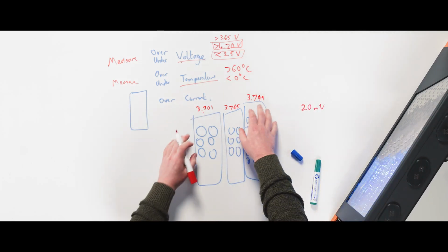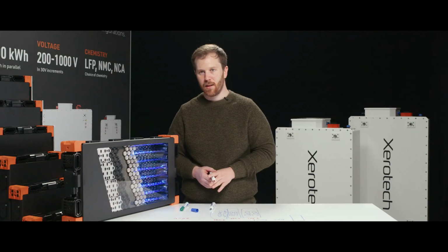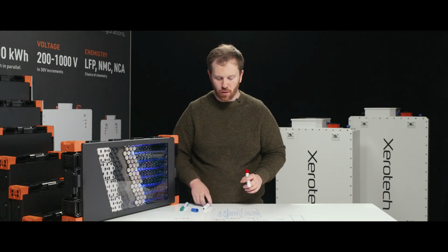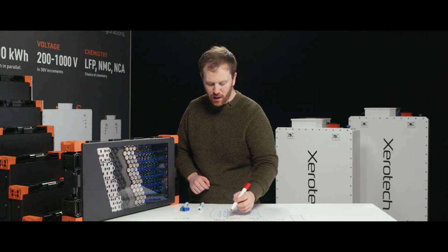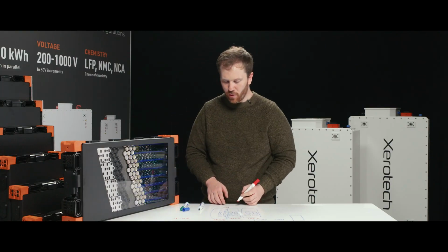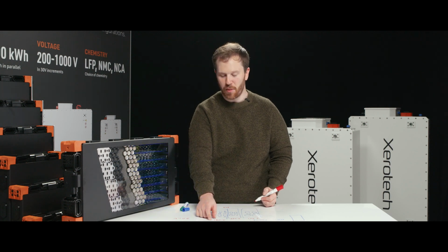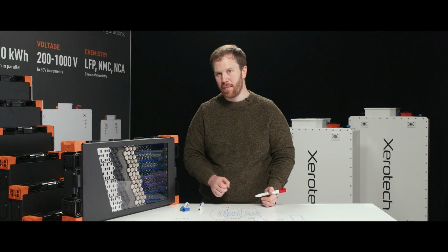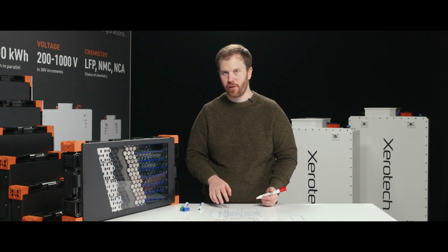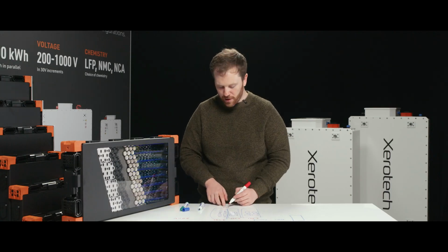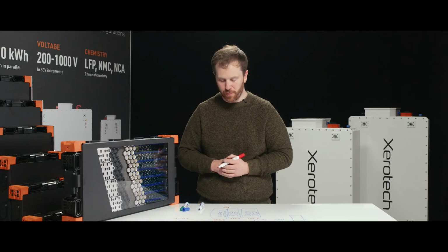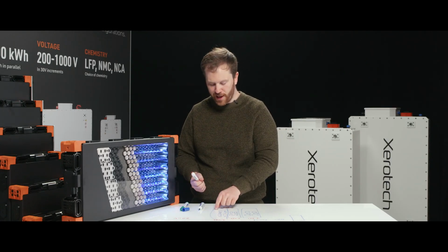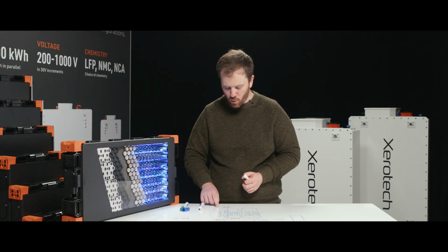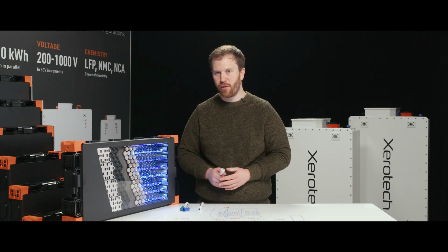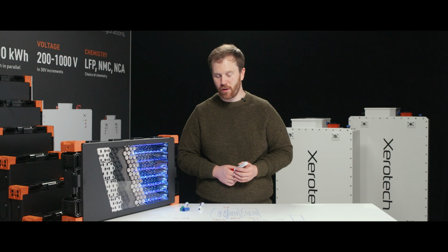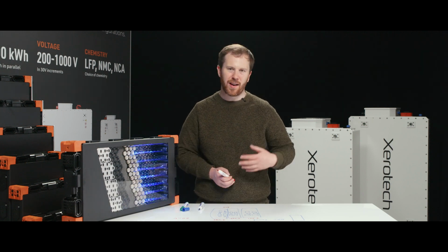Lower is better. So what we do in most cases is we have balancing circuits that can be either active or passive. So the vast majority of the world uses passive balancing, which is basically you have a small resistor on your BMS board that turns on and it burns off the heat, burns off the excess energy as heat. Active balancing is a bit better, not actually for efficiency reasons, although that's a nice help, but for power transfer. You're limited in the amount of power that you can burn here to usually about a watt for most battery systems, whereas active systems, they can shuttle energy from one bus to another. So you're actually discharging one bank and charging another, but also the amount of power that can be transferred is much, much higher. It'd be several watts or even tens of watts, if not hundreds of watts. So active balancing is nice in that regard, but it adds a lot of cost and complexity.